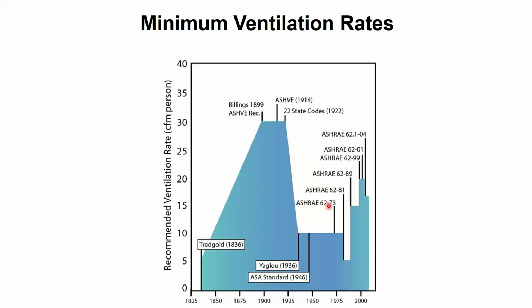Ventilation rates have changed a lot over time. This is a table, specifically for office buildings, and it's based on the ASHRAE standard. For brevity, right now we're around 17.5 CFM per person. I say around because it's additive, since 2004 for ASHRAE and 2006 for IMC. You take the per person, for an office that's 5 CFM per person, and this per square footage.